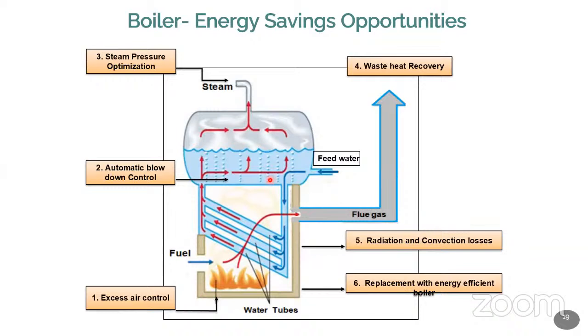Automatic blow down. Blow down is very important. The water used for the boiler should be DM water, because the salt content in the water should be within the limit. TDS value, salt content, pH value, everything is very, very important. Operating the boiler is not a simple thing. Maintaining the boiler is not a simple thing. So in most cases they have a separate RO plant, and sometimes a separate DM plant is also available, so that DM plant water is given as the input.